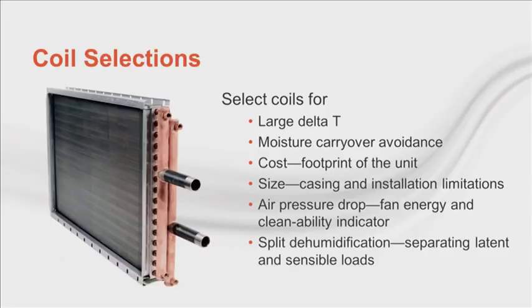It is also possible to put coils in series, for example by splitting the latent loads from the sensible loads to increase DeltaT. We went over coil fundamentals in the last broadcast, so I encourage you to watch that one for more information. Using lower flow, high DeltaT coil selections are particularly important for constant flow plants, but there are many advantages in variable flow plants too.